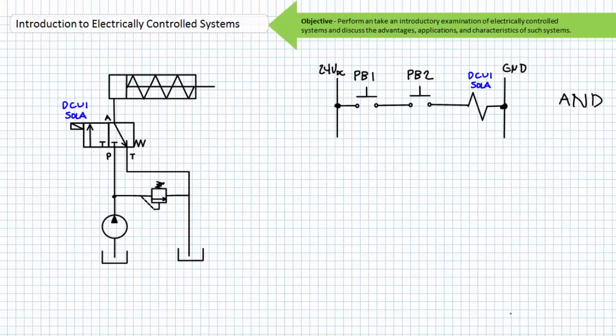Consider the simple addition of two switches to our ladder logic diagram, consisting of push button 1 and push button 2 in series. This is the logical AND operator. The only way an operator can energize the solenoid of DCV1 Sol A is if both push button 1 and push button 2 are simultaneously closed. This is a common safety feature for a device that requires an operator to have both hands cleared from the workspace prior to extending a hydraulic cylinder. An example might be a hydraulically driven press or a shear.